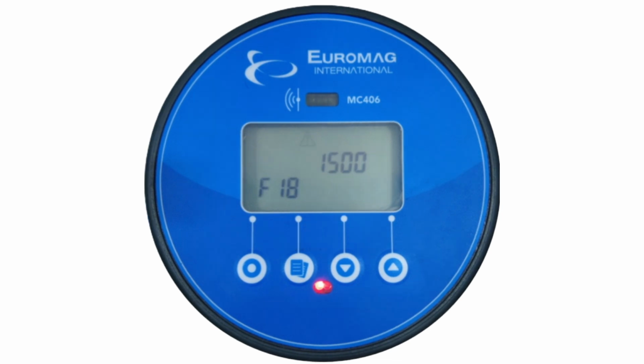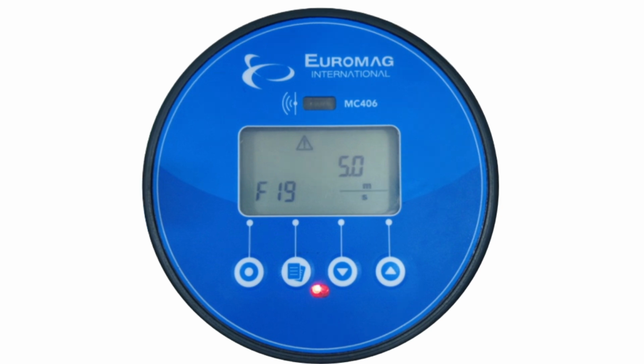Function number 18 will adjust the sensitivity level of the empty pipe threshold. Full scale is function number 19. The default full scale setting is 10 meters per second, which is just over 30 feet per second. In agriculture, pipeline velocities are much lower. Adjusting the full scale value will also affect an analog 4 to 20 mA setting and peak cutoff filters.